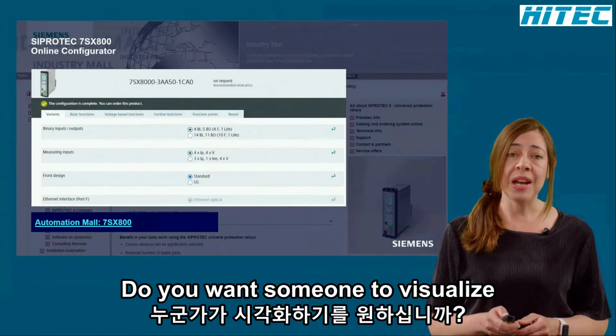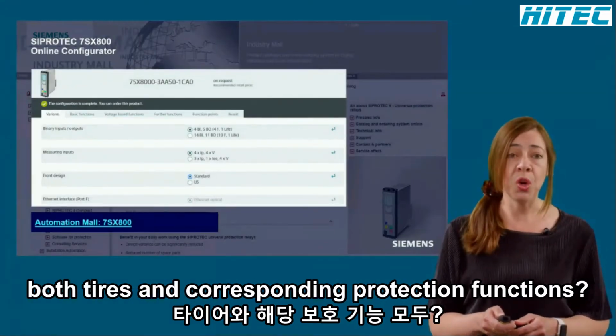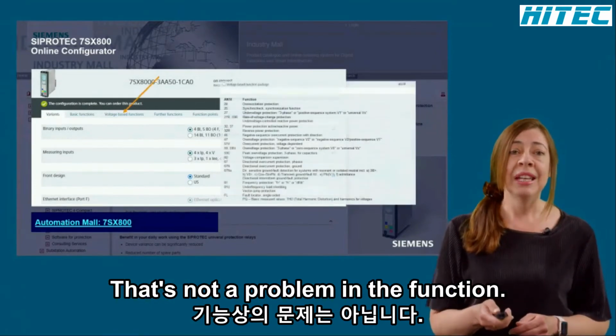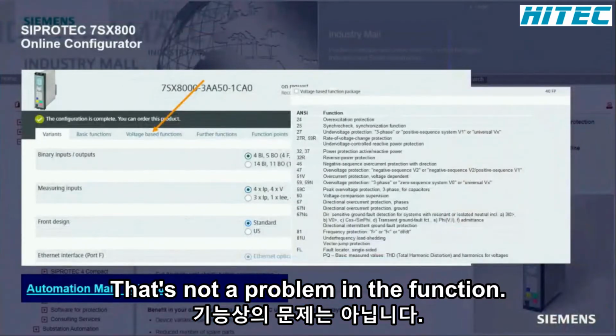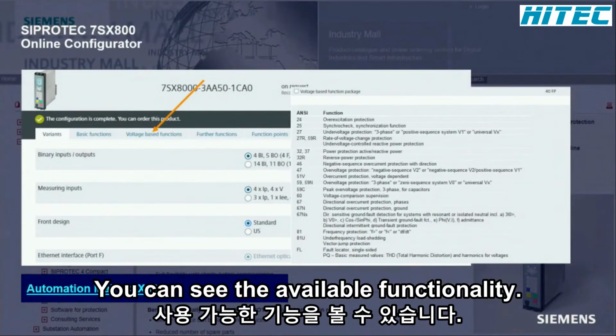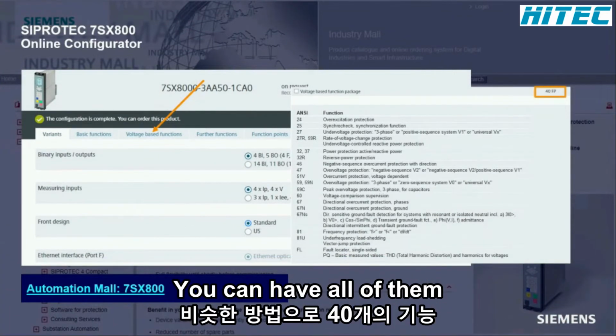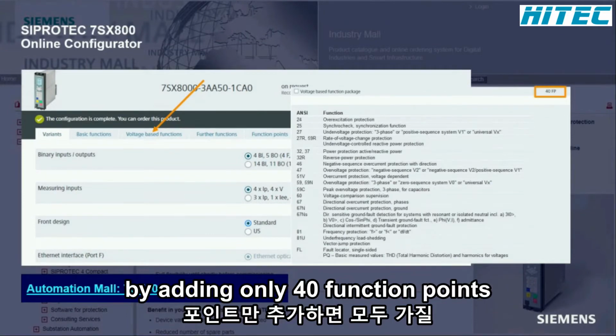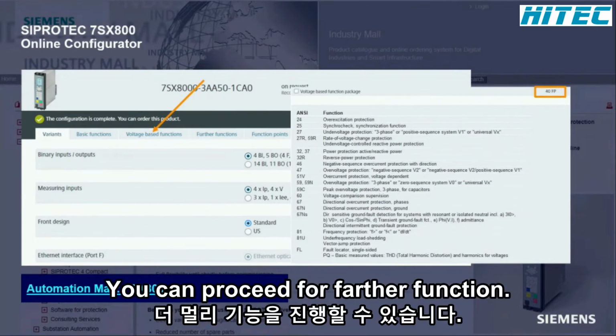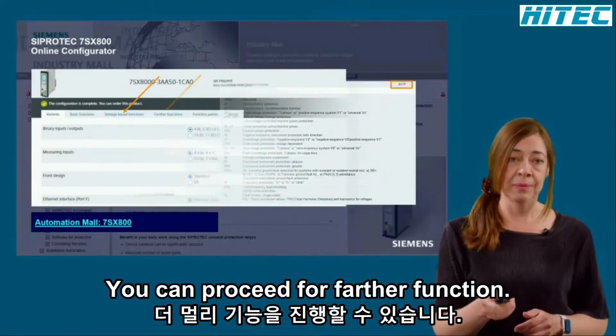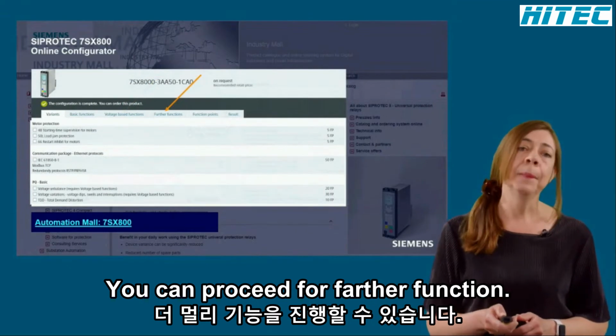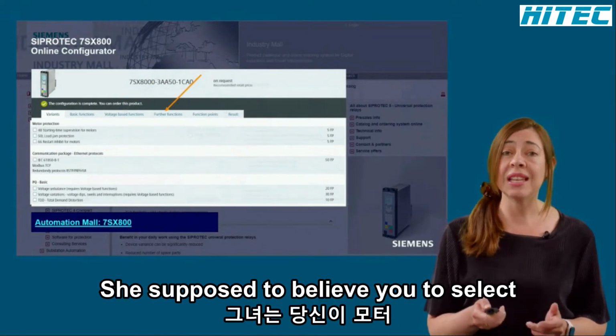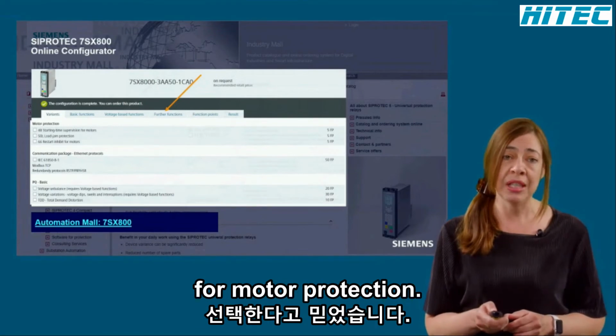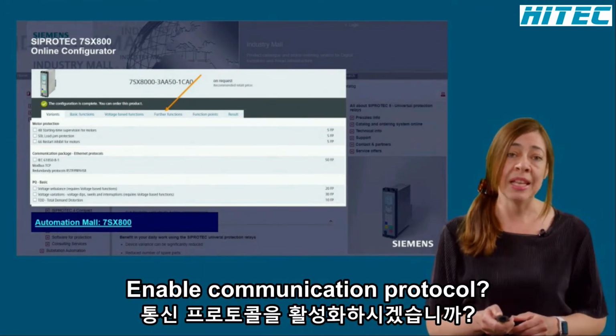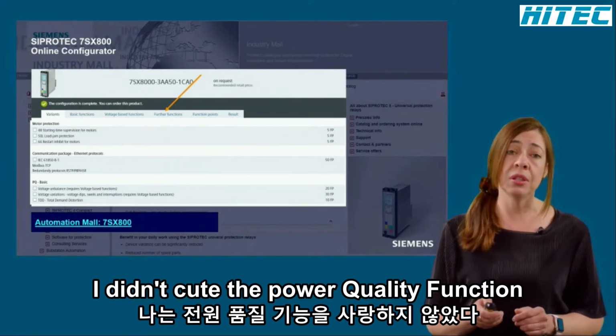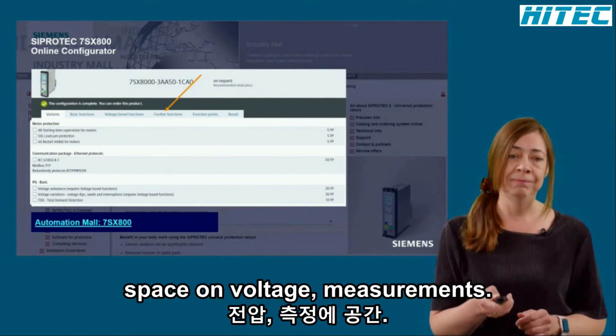Do you also want to visualize voltages and corresponding protection functions? That's not a problem. In the voltage-based function tab, you can see the available functionality. You can have all of them by adding only 40 function points. In a similar way, you can proceed for further functions. Here, you have the possibility to select specific functions for motor protection, enable communication protocols, and include the power quality functions based on voltage measurements.